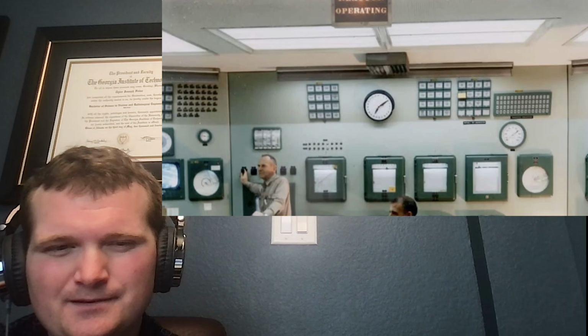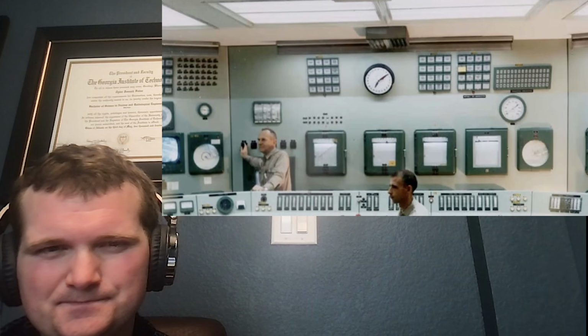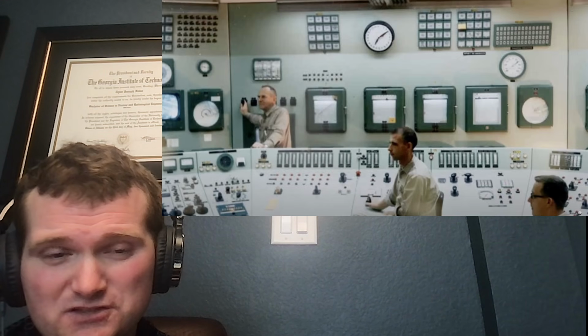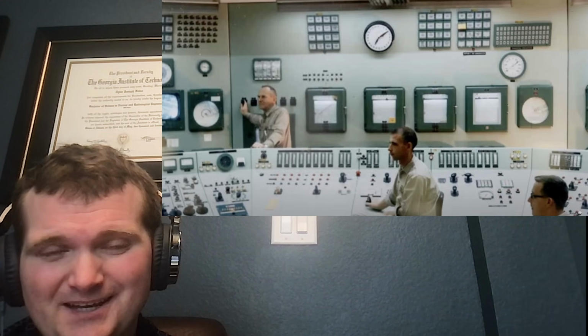The reactivity levels and the detection of fission product contamination in the cover gas indicated that fuel melting had occurred. Since a significant amount of fuel melting could change the pressure characteristics of the core. Now this would take more time to make that assessment of how much fuel damage has occurred. That can take hours to days. The emergency shutdown and making the decision you have a leak, we're talking in a matter of minutes, typically less than 5 minutes.